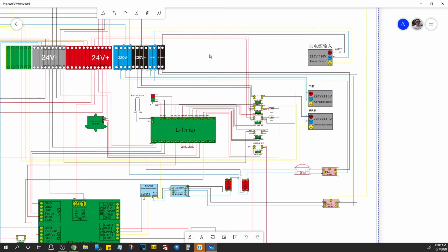So anyway, just to recap, the main power goes in from the plug into the jack, through the breaker, through these two filters. One branch powers the control and the rest of the laser. The other branch powers just the laser power supply and the chiller, if it is that model. So for the chiller and the laser power supply to work, both of these switches need to be on. The emergency stop needs to be good, and your breaker needs to be good. So those are the things that I would check first.